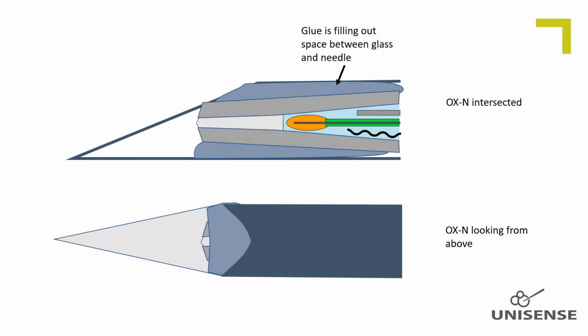We make needle-embedded versions of the oxygen sensors in order to give some protection to the sensor tip from being damaged. We make them in two different versions, OX-N and OX-NP. The latter is made for piercing membranes. This is a schematic drawing of the tip of OX-N and OX-NP sensors. The needle protects to some extent the glass, but the sensor tip is still fully exposed to the sample solution. The needle and the glass part of the sensor are glued together inside the needle, so no sample liquid will intrude into the needle. This would otherwise cause a huge carryover effect.